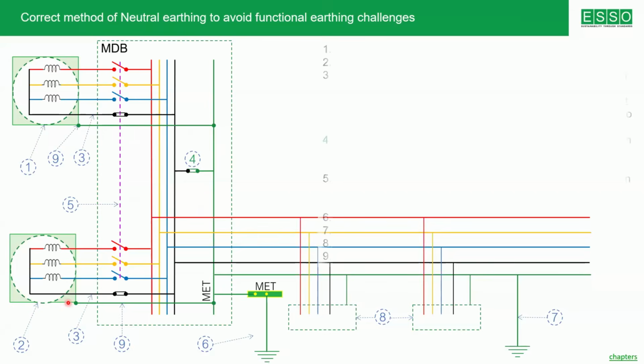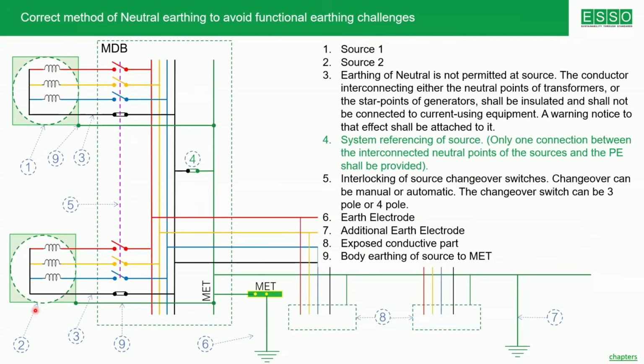Example, you have, let us say, serial number 1 and 2. These are source 1 and source 2. Maybe you have multiple sources in a system. You see the neutral is directly, this dotted line is the main distribution board. The neutral is directly connected to the bus bar through a link. 3-pole switches are used. Then the neutral and the earth bus bar in the main distribution board, serial number 4. This is system referencing. This is the neutral earthing which is made inside the main distribution board. Only one connection between the interconnected neutral point of the source and the PE shall be provided.